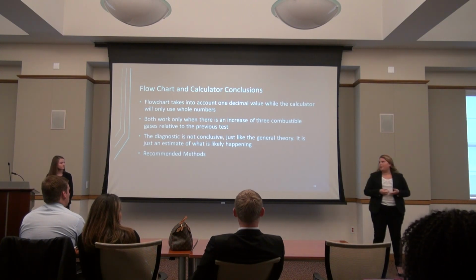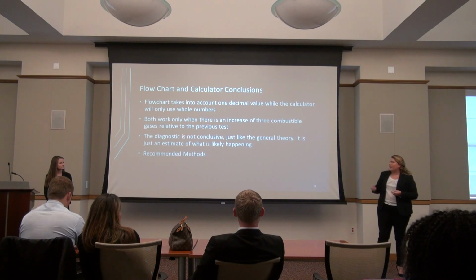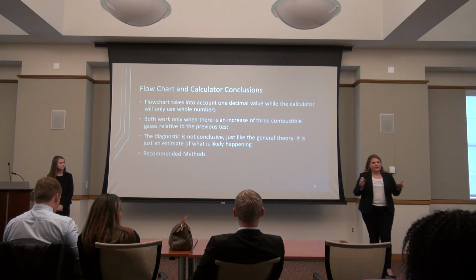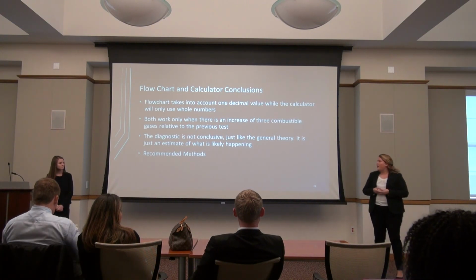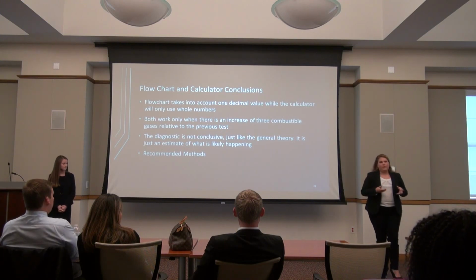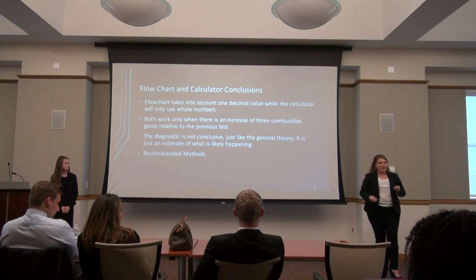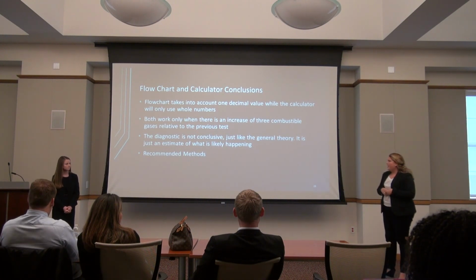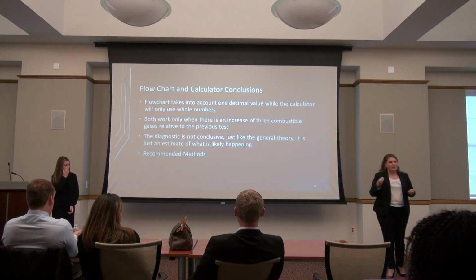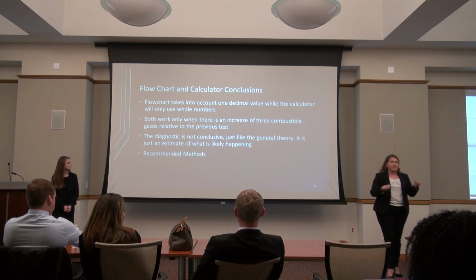One disadvantage is that the flowchart takes into account decimal values, while the tool only takes whole numbers. They both work when there is increased gas, not necessarily when the methane, ethylene, and acetylene decrease. And diagnostics, as we know, are not necessarily conclusive. Just because we get one result doesn't mean it's actually happening at the moment, but it's very likely that it is.